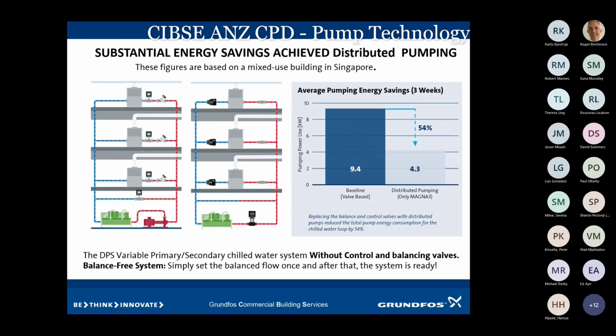It's another system which they've now been using in Asia and Europe. In this particular case, they have done away with the valves, and again, this is going back to pumps now with controls and extra inputs and outputs that are available. In this case, we take out the modulating valve and we take out the balancing valve. The modulating valve would have been getting a signal from a duct temperature sensor or from the BMS to open and close. That signal now has been sent into the air handler pump. So that air handler pump now replaces the valve. Inside the pump, you set the maximum flow rate, so that's your balancing. All you need to do now is put a check valve on each air handler, set the pump to the flow rate that is required, and then away you go from there.